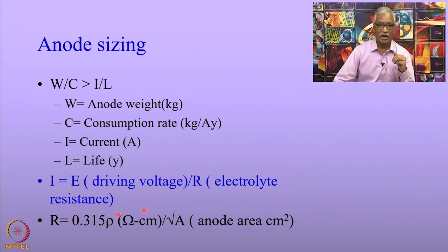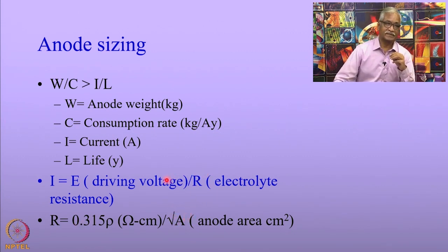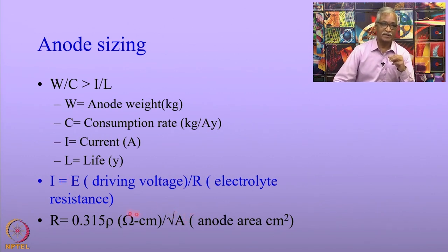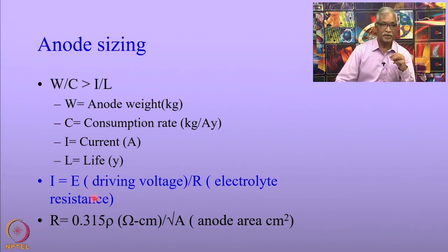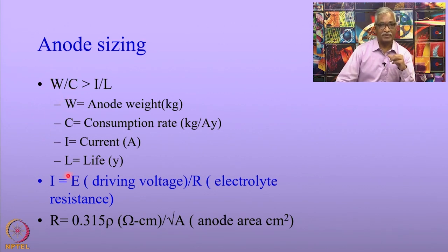If the area of the anode becomes smaller, you will not get sufficient current to protect the structures or the driving voltage will be reduced. So the sizing of the anode is based on both the weight required to protect for the given life and the driving force required to drive the needed current for the structures.